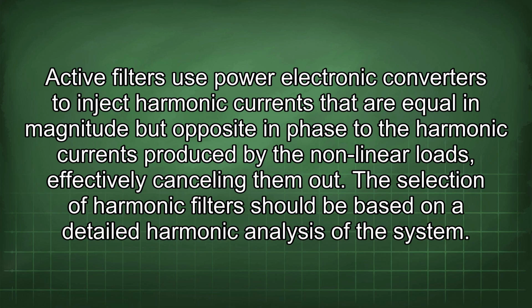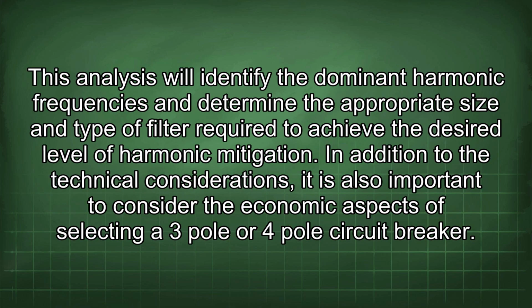The selection of harmonic filters should be based on a detailed harmonic analysis of the system. This analysis will identify the dominant harmonic frequencies and determine the appropriate size and type of filter required to achieve the desired level of harmonic mitigation.